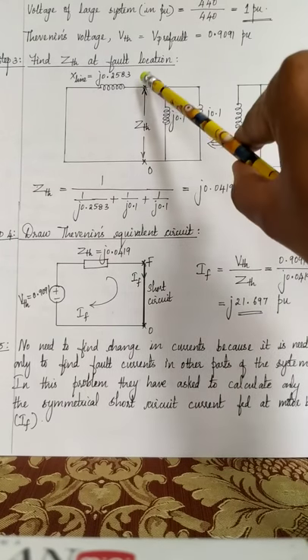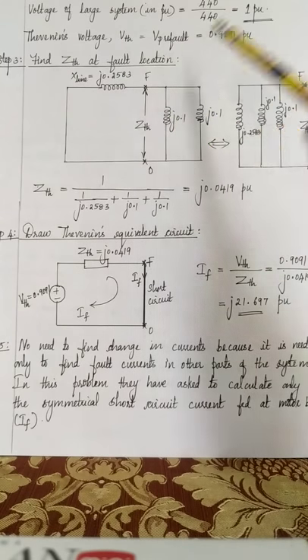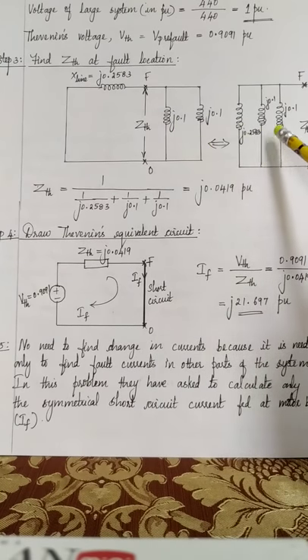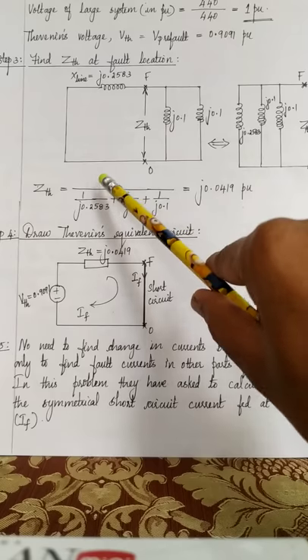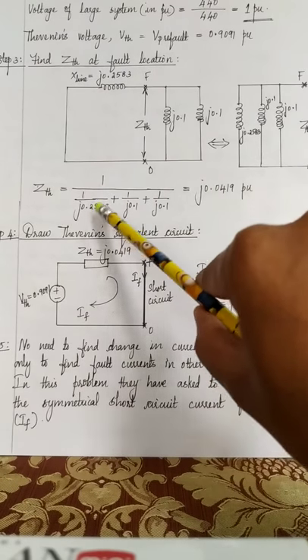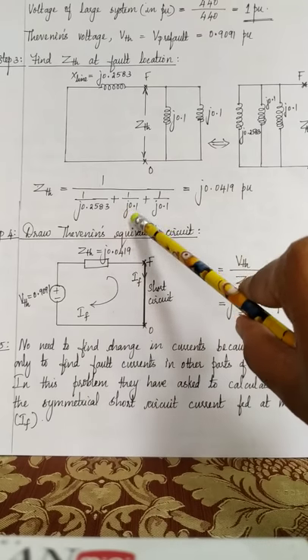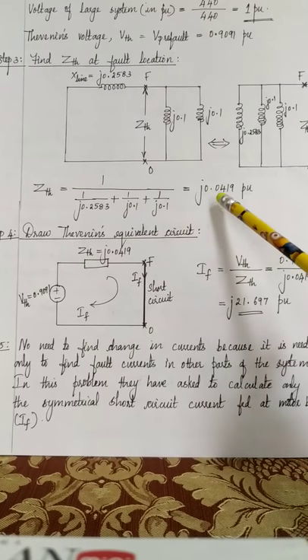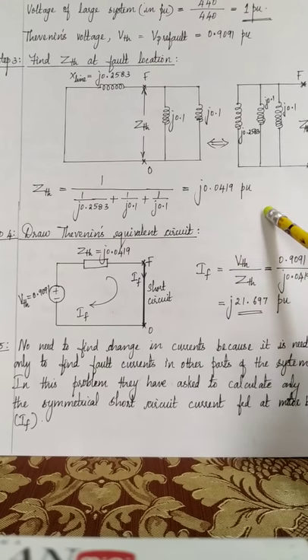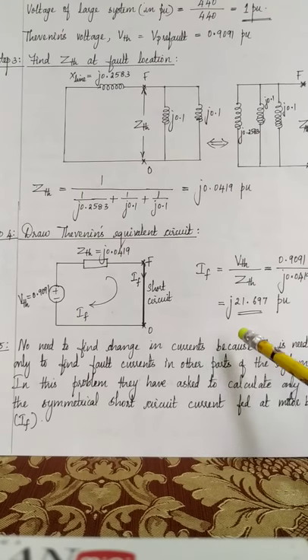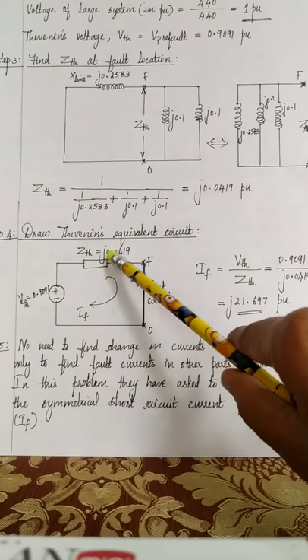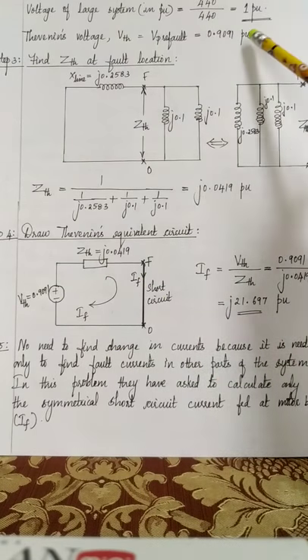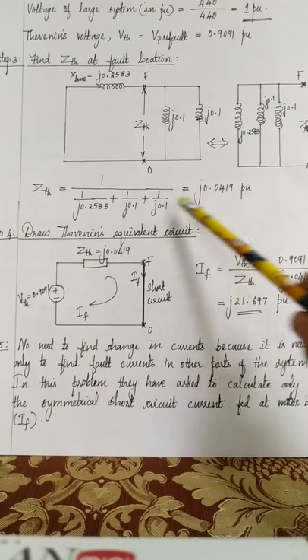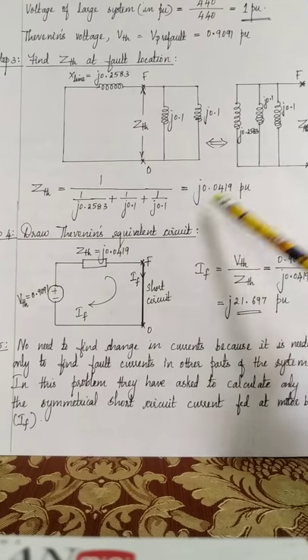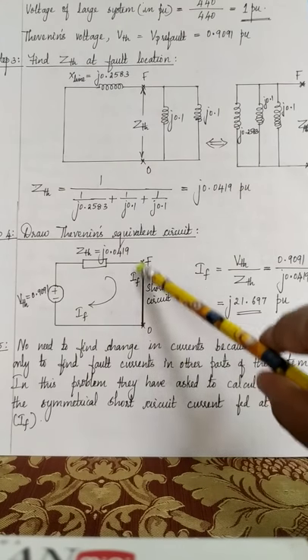Both are similar because here it is a separate point, separate node. So the three reactances are coming in parallel, J0.2583, J0.1, J0.1. So ZTH is the equivalent impedance, which is 1 by J0.2583, 1 by J0.1 plus 1 by J0.1, which will give you ZTH as J0.0419 per unit. So now draw the Thevenin's equivalent circuit. VTH in series with ZTH. VTH is 0.9091 per unit. ZTH is 0.0419 per unit. And represent the short circuit at the fault terminals.